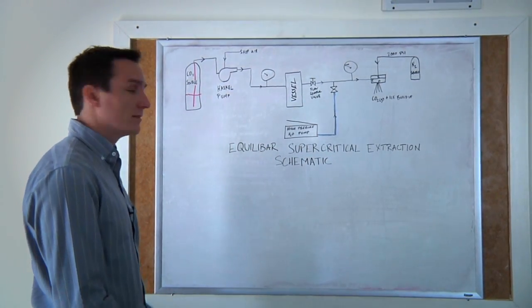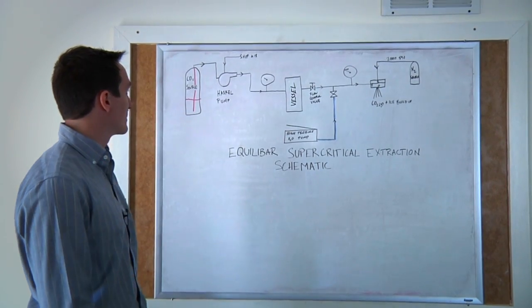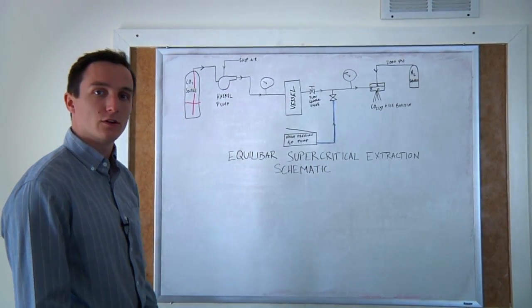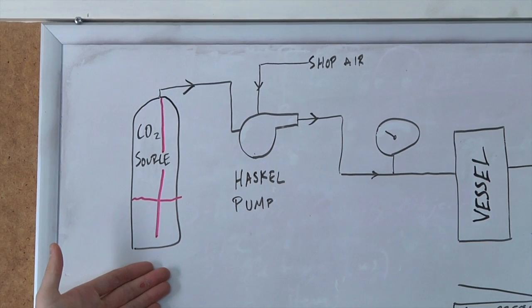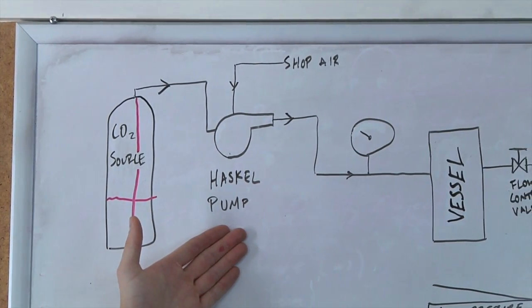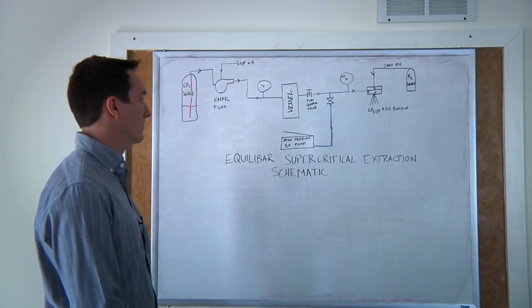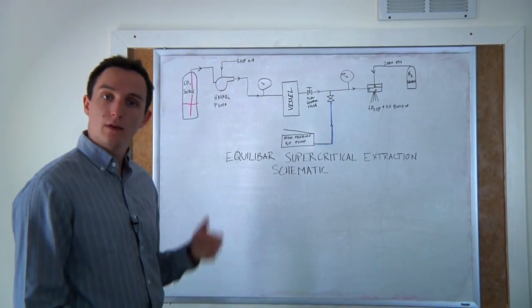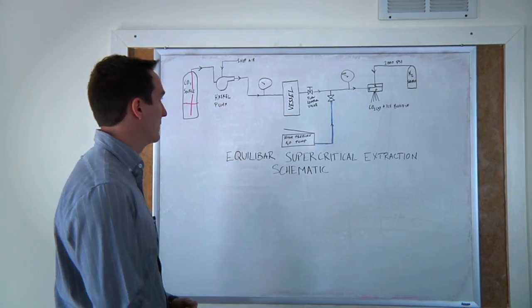So to start, we have our CO2 source tank, which has a siphon tube that draws liquid carbon dioxide from the bottom of the tank. It goes to our Haskell pump, which has a 25 to 1 ratio in which we plan to output the pump at around 2,000 psi.